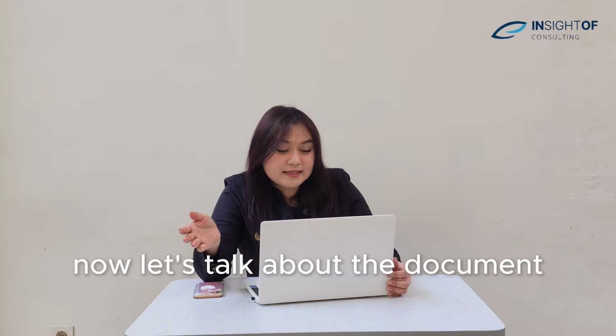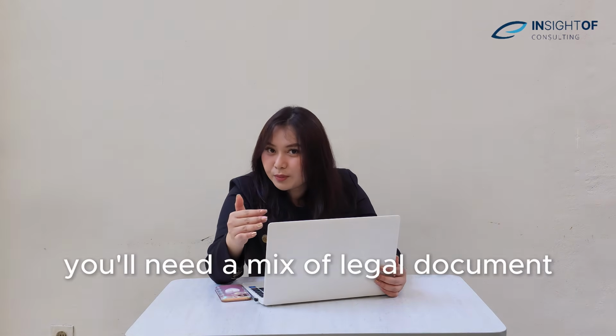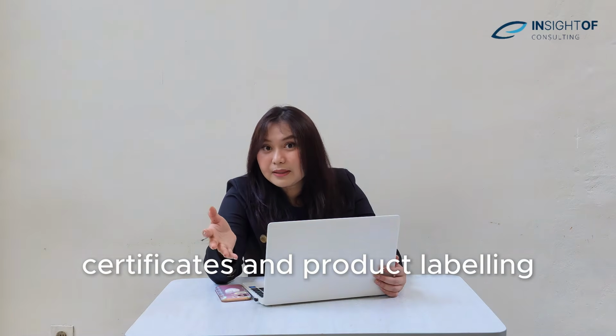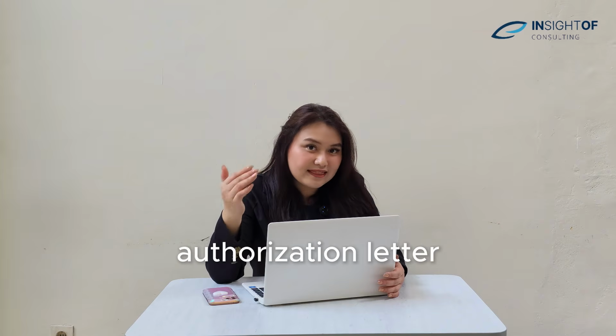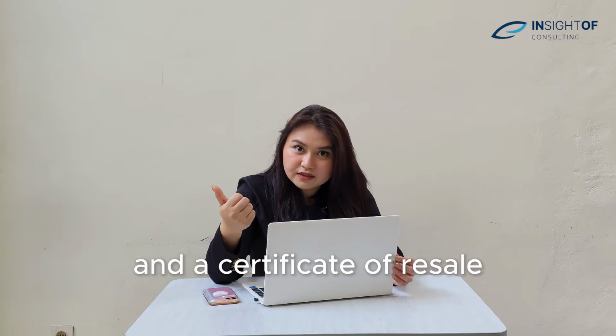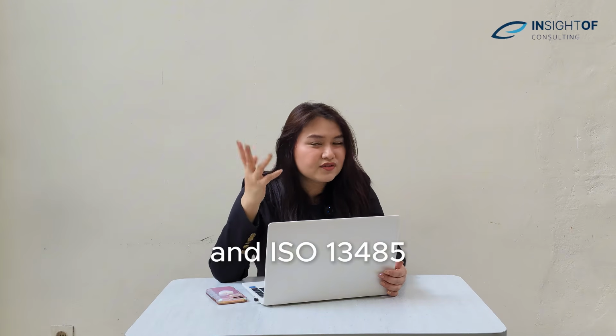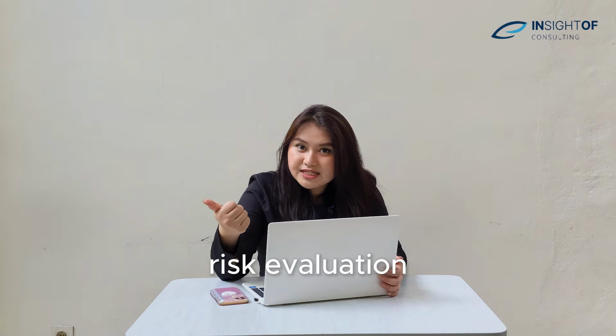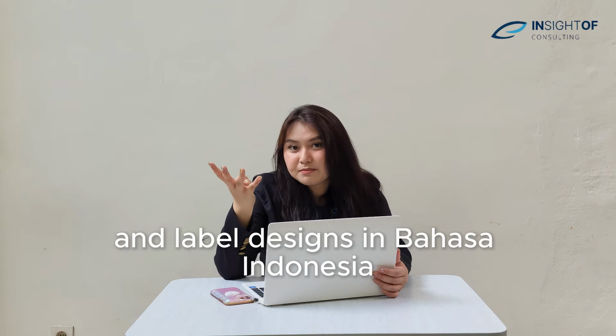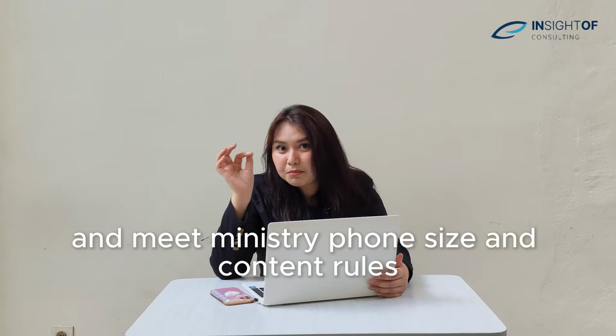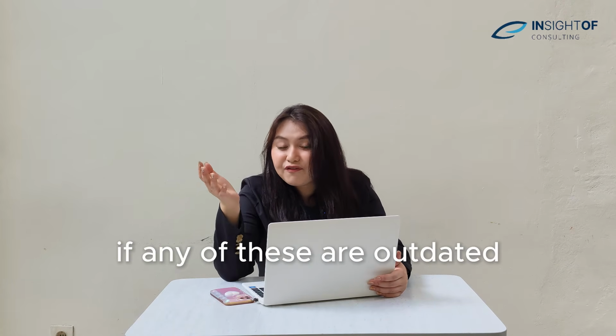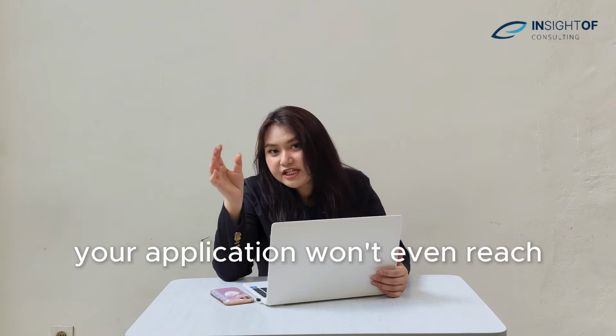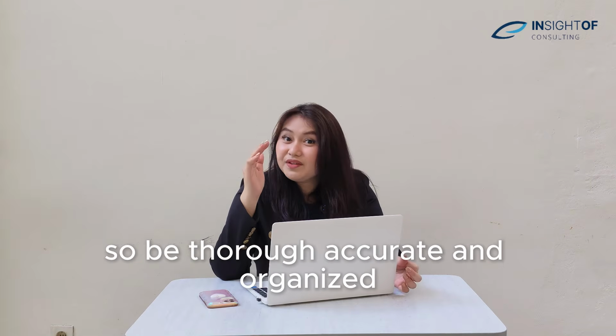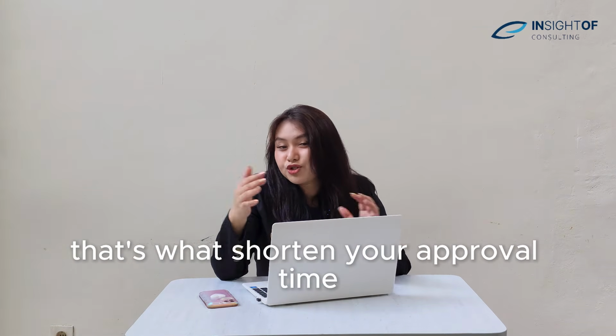Now let's talk about the documents. This is the part that causes the most delays, but it's also where we help the most. You'll need a mix of legal documents, technical files, certificates, and product labeling. Almost every device requires an authorization letter from the manufacturer, a certificate of free sale, ISO 13485, and a detailed product summary. Then there's your declaration of conformity, risk evaluation, post-market surveillance plan, and label designs in Bahasa Indonesia. And yes, every word must be translated and meet ministry font size and content rules. If any of these are outdated or incomplete, your application won't even reach the review stage. So be thorough, accurate, and organized. That's what shortens your approval time.